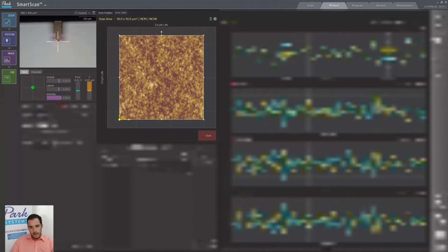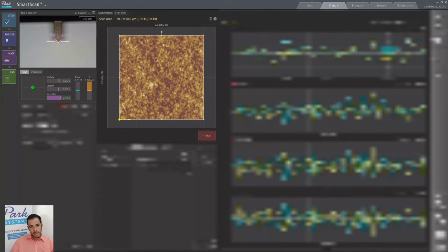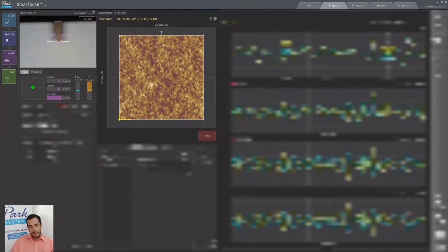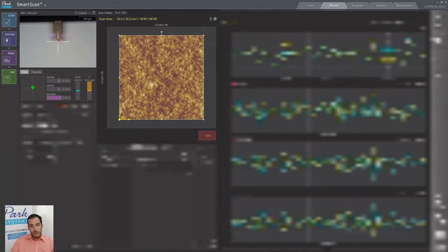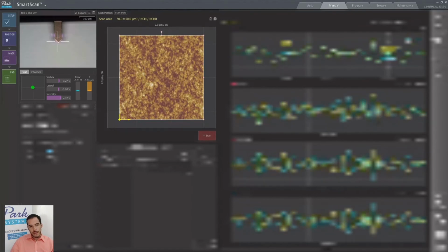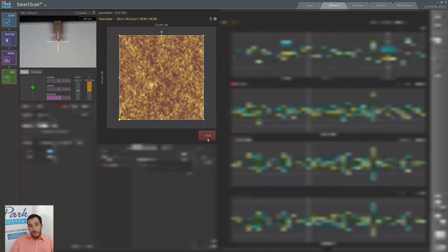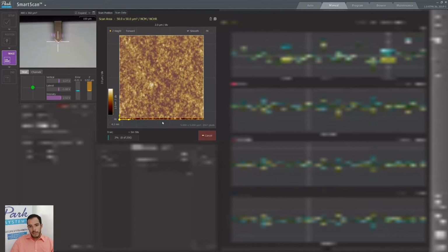Just to make this comparable with the previous image we have, we're going to use the same settings. So 13.9 nanometers as a set point and 0.7 for the Z-servo gain for both of them. And when we are ready, we just have to go back to the scan button and click on it and we'll start scanning.